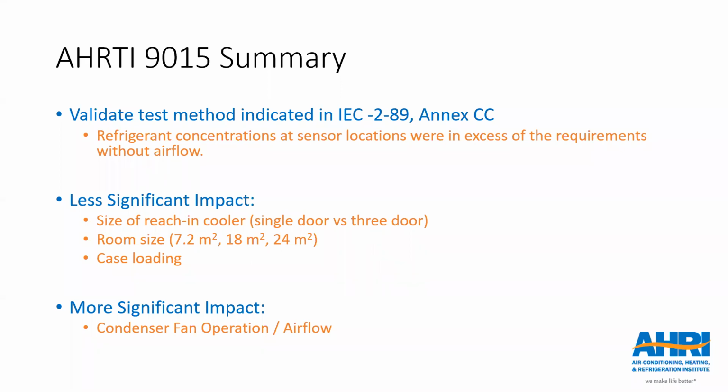the factors that we really didn't see having a significant impact on the project were the single door versus three door. We saw very similar results. We also didn't see a difference really going from the various room sizes when we scaled the refrigerant charge with that. And then we didn't see a difference with the case loading. Like I noted, there were some slight differences between them, but not enough to really have a big impact on compliance results, regardless of their statistical significance.